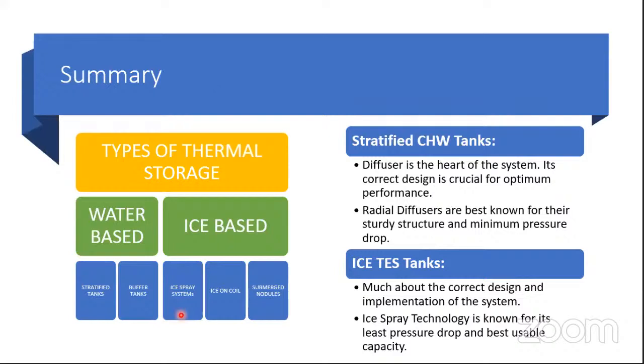I would now like to quickly summarize what we have gone through in this presentation. We generally understood the types of thermal storage system. Two types: water based and ice based. We talked about stratified tanks, we talked about buffer tanks, and we talked about ice based systems, ice on coil technology, and submerged nodules as a category. And that's just an opinion, but in a stratified thermal storage tank, the diffuser is very important. The diffuser is the heart of the system. Like I'm again saying, that's the key. Its correct design is crucial for optimum performance. And radial diffusers are best known for their sturdy structure and minimum pressure drop.